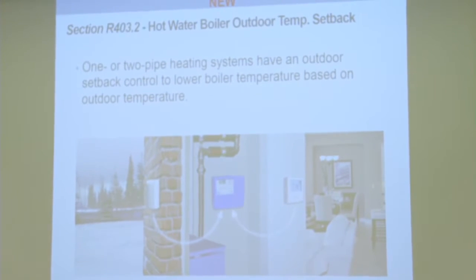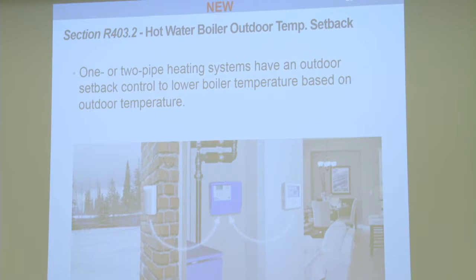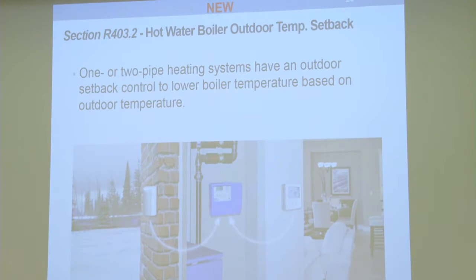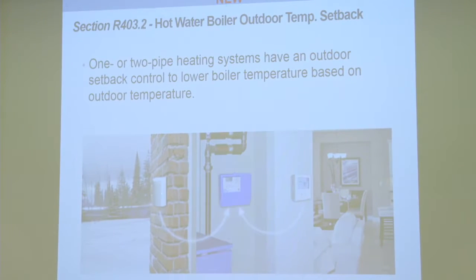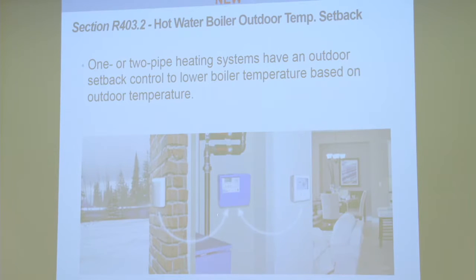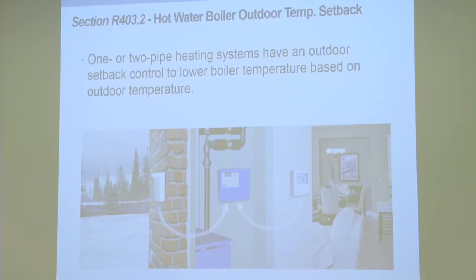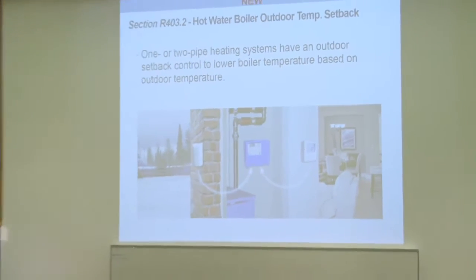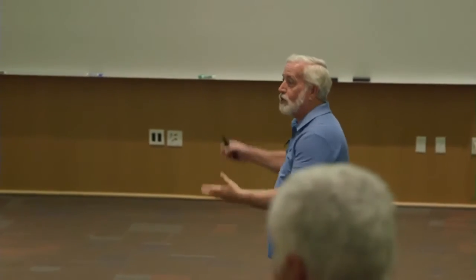This is a good one. Outdoor reset or outdoor temperature setback. Basically, if you're running a boiler, you do not need to run as hot of temperatures when it's 40 outside as you do when it's 10 outside. And so outdoor reset simply has a control with a sensor outside that communicates with your thermostat, your boiler, and everything. And as it's warmer outside, it reduces the boiler temperature. And it's been around forever, and it's really important if you're having radiant heat, because if you're running the hotter temperatures, you overshoot when it's mild. And so what does everybody have to do? They have to open the windows because the house gets so hot, and so it just modulates water temperature based on outdoor temperature. That's a good requirement.